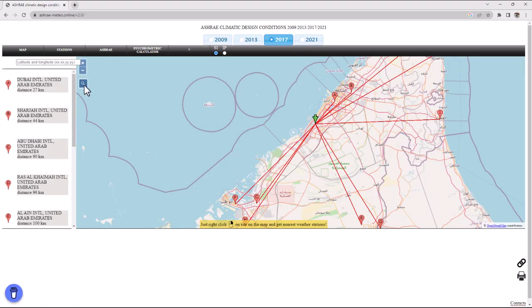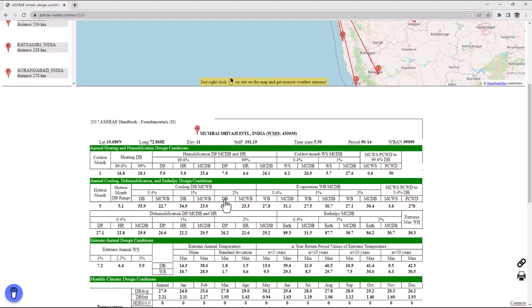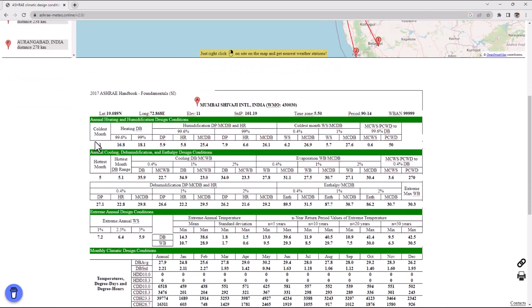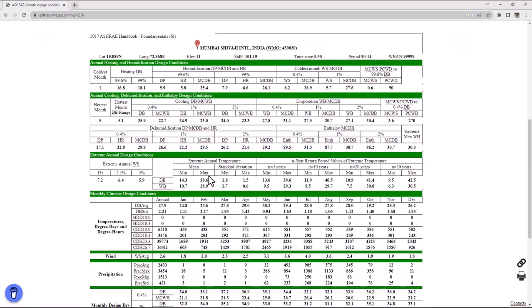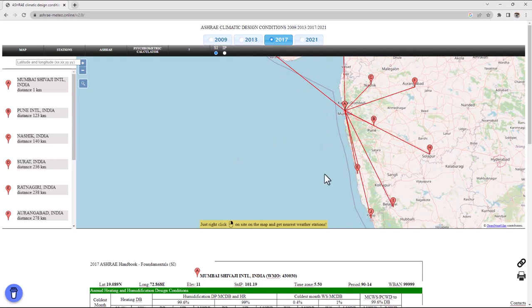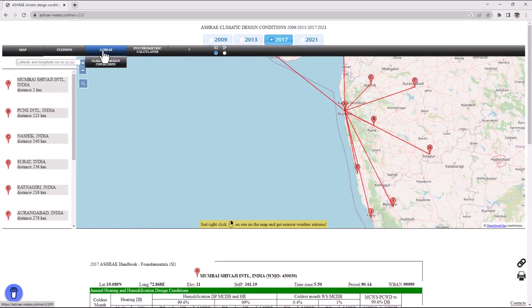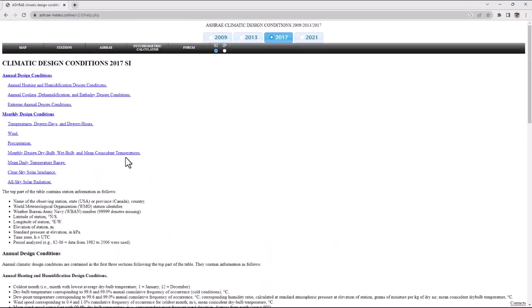You can always select 2013 or 2009 ASHRAE data online instead of going to the book itself. One last example — Mumbai, India. You'll find different weather station options; Station A is the closest at 1 kilometer, giving you Mumbai Airport data with heating, cooling, extreme annual, and monthly design conditions. If you want to understand each variable — like wind speed or mean coincident dry-bulb — the ASHRAE Climatic Design Conditions page explains each one in detail.